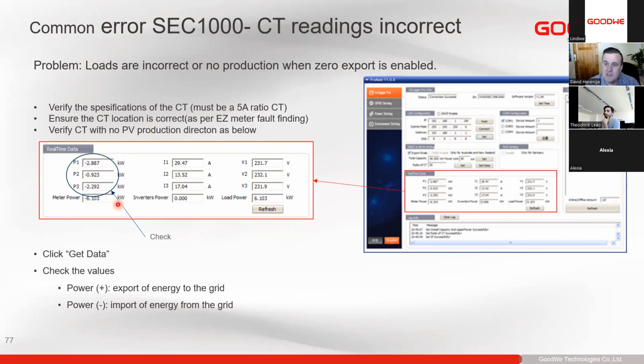What you can also do is a clamp meter test: use your clamp meter and see if it confirms that this is correct. Another test that I like doing is I take the current times the voltage, and that should give me this value within margin based on the power factor. So if I take 29 amps times 231 volts, it's definitely not close to 2.8. That's a power factor of probably 0.5. So very often we can have a very bad power factor.